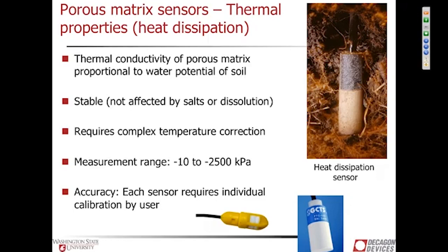The real difficulty for most users with these sensors is that each sensor requires individual calibration. So these come without an accuracy spec and without a calibration, and so you have to go through the steps to calibrate these yourself, and the accuracy that you would get out of each sensor depends on the quality of the calibration that you implement. And so this is fine if you have some skilled graduate students or technicians that can do this, but it adds a lot of time and expense to actually determine those individual calibrations for each individual sensor.